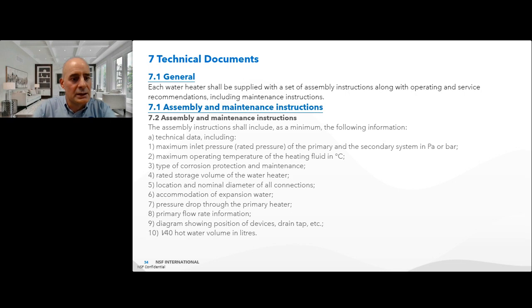So technical data, including maximum inlet pressure, so rated pressure of the primary and the secondary system in pascals or bar, maximum operating temperature of the heating fluid in degrees C, type of corrosion protection and maintenance, the rated storage volume of the water heater, location and nominal diameter of all the connections, accommodation of expansion water method, pressure drop through the primary heater, primary flow rate information, diagram showing positions of the devices, so the draining tap, etc., and the V40 hot water volume in litres.